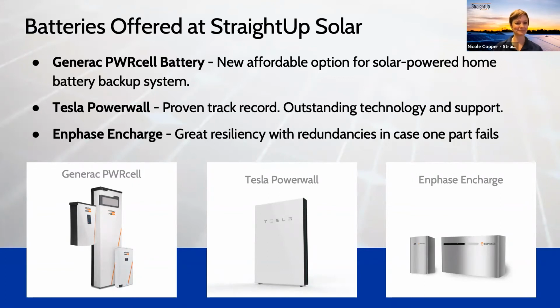I just want to address a question I saw in the chat, to help bring this alive for everybody. We can do any of these battery cabinets in an outdoor installation. The reason we recommend indoor installations is that there are heating and cooling systems in each of these battery options, and maintaining that temperature costs you kilowatt hours of battery capacity. So to get more life out of your battery, or more runtime on a daily basis or in a backup capacity, we usually recommend installing them inside. But again, we can work with you on your individual installation to see what works best for you — just reach out to us if you want to go that route.